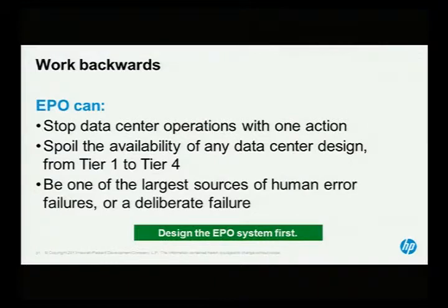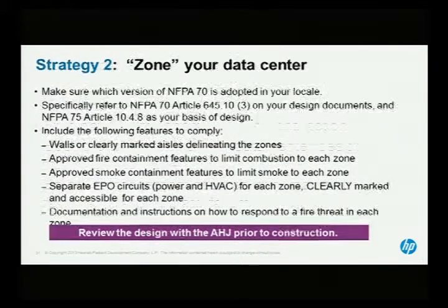I strongly suggest that you design the system with a test feature. So you can put it into test mode, test the whole thing out, make sure it works, or if you have to have an add-on, in other words, you're extending the area of coverage, you can put it into test or defeat it, so you can tie in the new circuits, put it in test position, test the new circuits before you put it back online. Very common fixes. Strategy number 2, zone your data center.